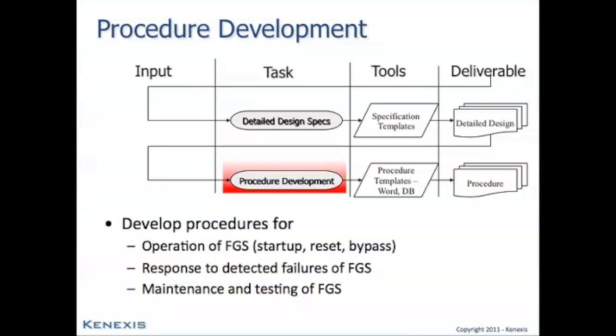After the detailed design is complete, or sometimes in parallel with the detailed design, is the development of procedures by which the FGS system will be used. There are multiple procedures that need to be developed at this phase and considered prior to more time-critical steps in the life cycle, such as startup and operational phase. The development of these procedures is an important task because it allows the design team to think through how the FGS system is going to be interacted with.